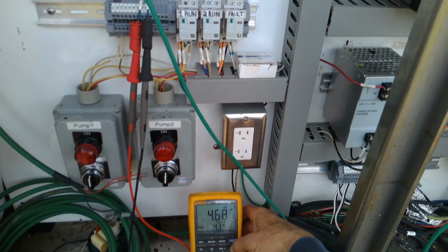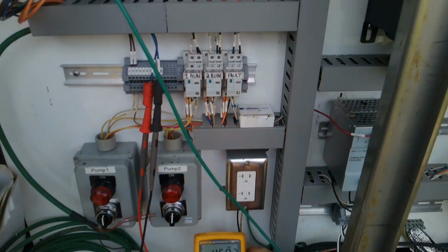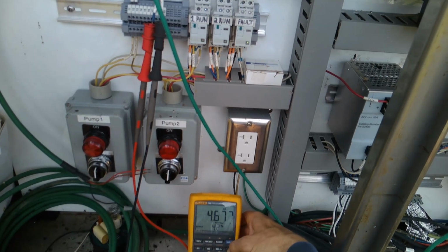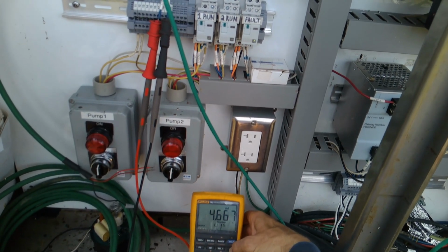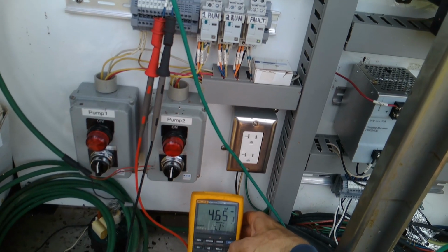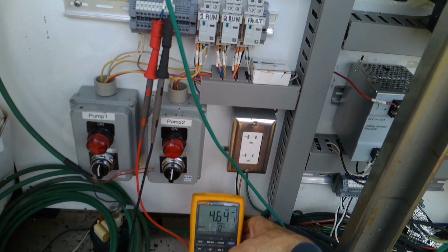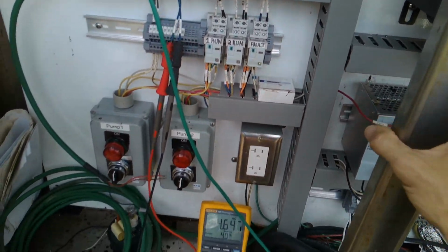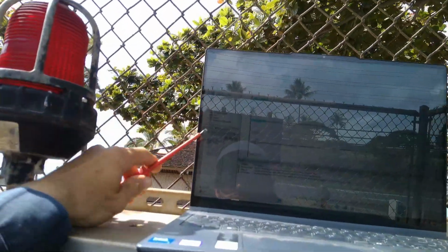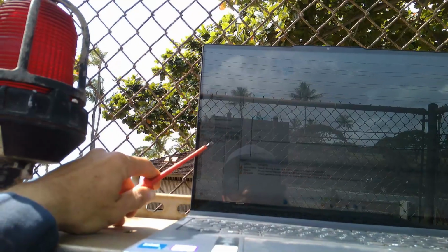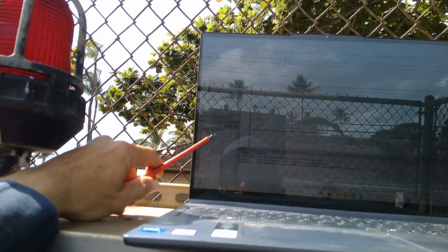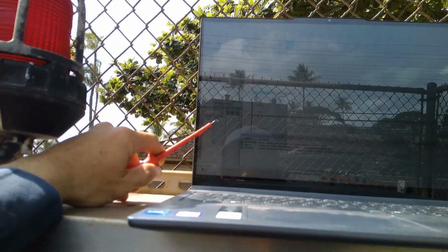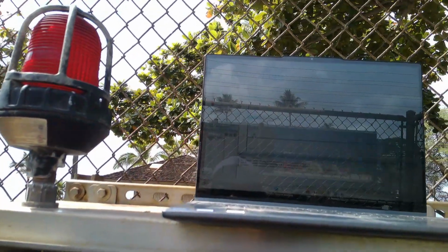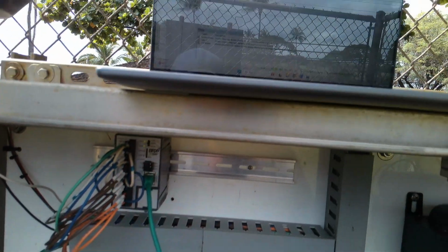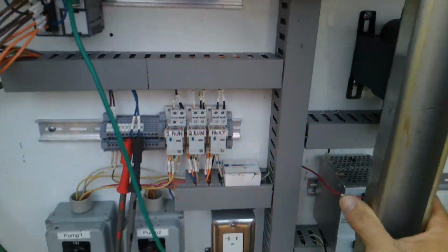Let's park it right at 4%. Keep going. There's 4%. So it's pumping out 4.647 milliamps. And if you look at our raw value there, the last two digits are bouncing between 60 and 58. So that's incredibly stable. Let's try put it in auto and see if we still get all that chattering and bouncing.